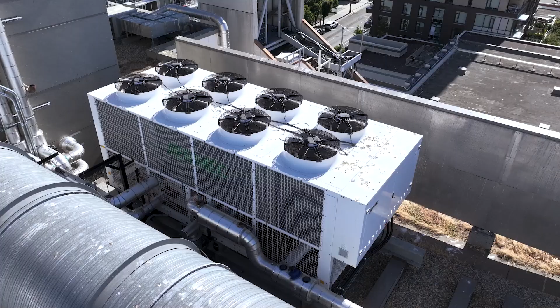The project started with a large scope of demo, so there were 3 crane lifts over the duration of the project. The first crane lift was to remove the demoed pipe and the disconnected heat pump that existed on the rooftop—a 20,000 pound piece of machinery that had to be cantilevered over the street. It was a pretty dangerous lift, so there was lots to engineer to make sure it went properly. Originally, that piece of machinery had gone up with the help of a building crane in the center of the building. We didn't have that option, so we managed it from the side of the road with lots of cantilever. It went off beautifully, but we definitely maxed out our capability.